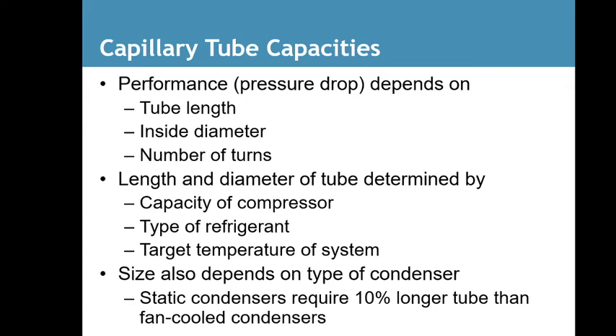Think about running down a long hallway as fast as you can, and you come to a 90-degree bend. Well, if you don't hit that wall, you're not going fast enough. So it's hard to make a sharp turn. So you will lose some of the refrigerant flow. You see a lot of these coils coiled up because when they design these, they can't tell exactly how it should work. But you could actually put bends in a capillary tube to make less refrigerant go through. So there are ways that you can tune a system as well with a capillary tube.